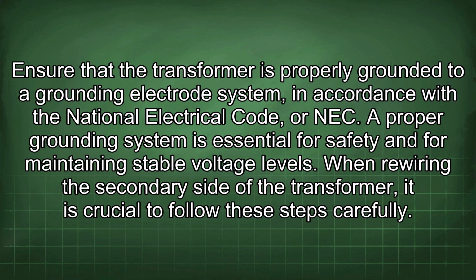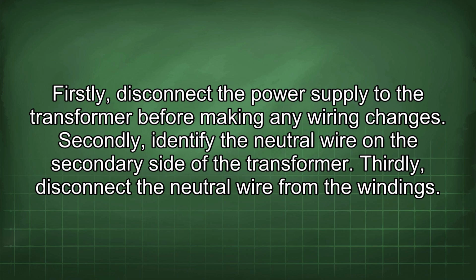A proper grounding system is essential for safety and for maintaining stable voltage levels. When rewiring the secondary side of the transformer, it is crucial to follow these steps carefully. Firstly, disconnect the power supply to the transformer before making any wiring changes. Secondly, identify the neutral wire on the secondary side of the transformer. Thirdly, disconnect the neutral wire from the windings.